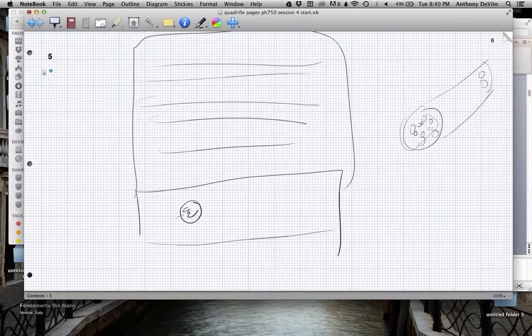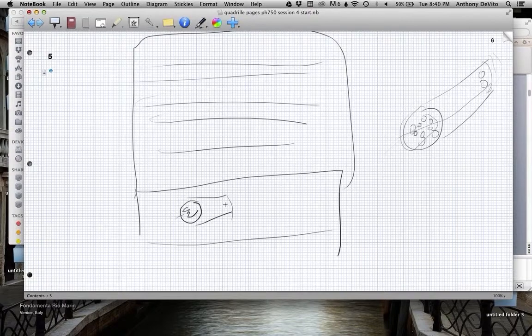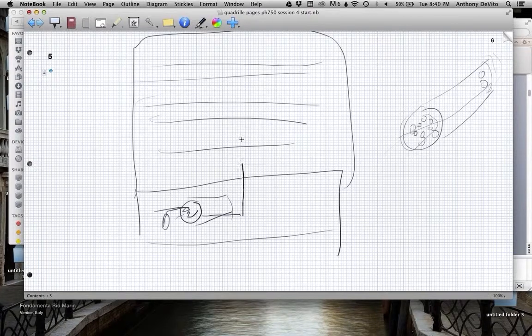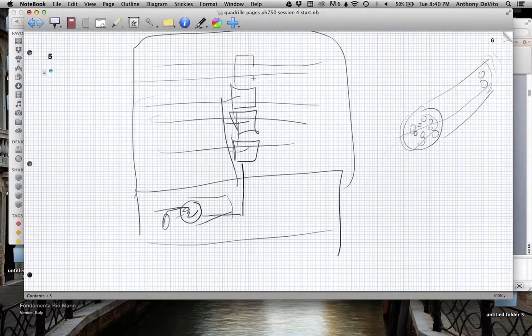So the Freon goes into the tubes and comes out the other side, right? You evaporate the Freon by releasing it into these tubes. But now on the outside of those tubes, or that coil, is water. You pump water in, pump water out. It chills the water to 45 degrees. You send that water up to devices, boxes on each one of the floors. Cold water, 45-degree water, right?